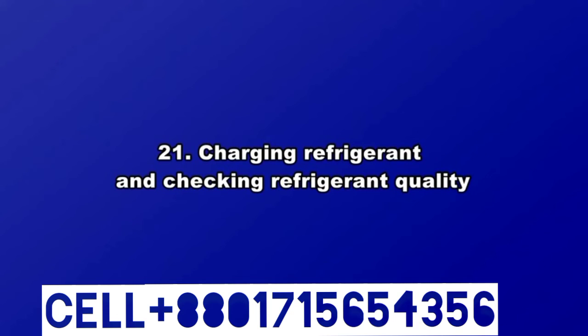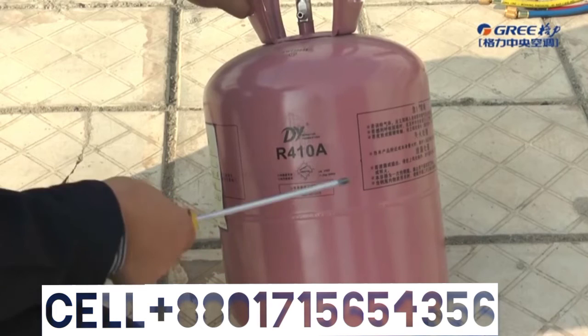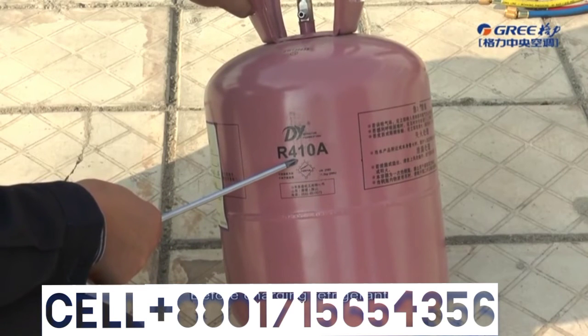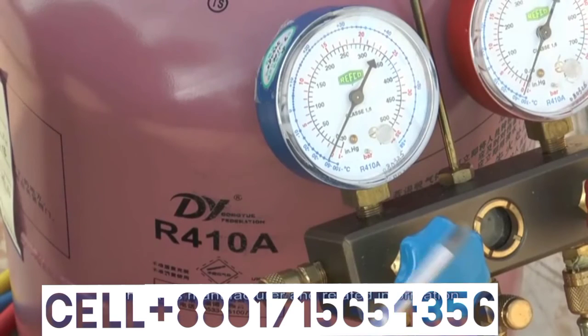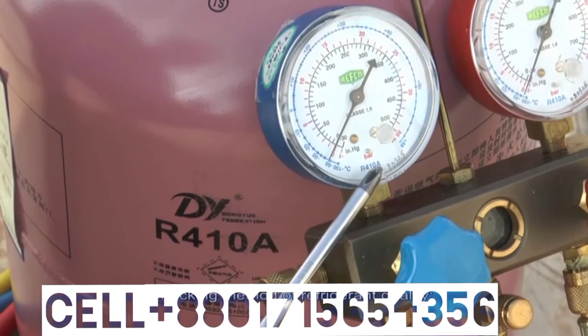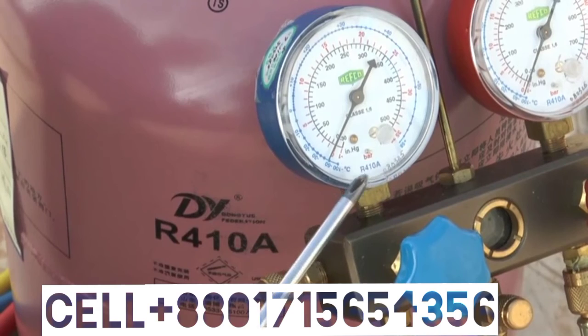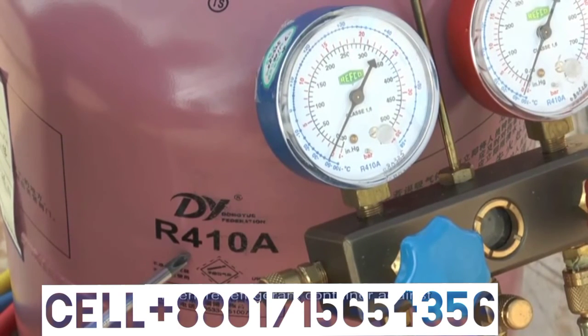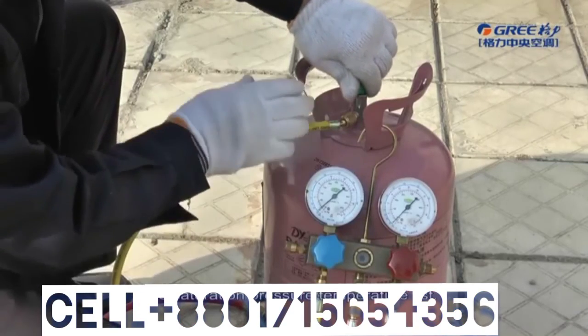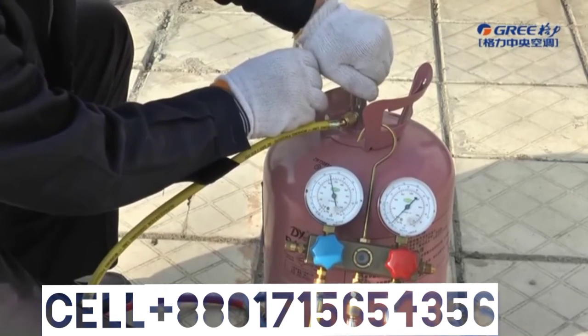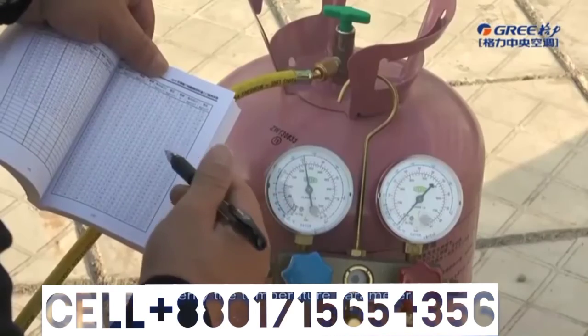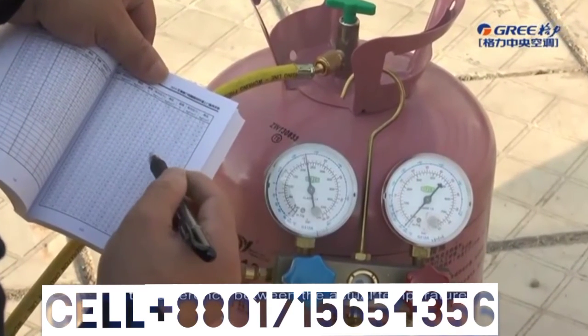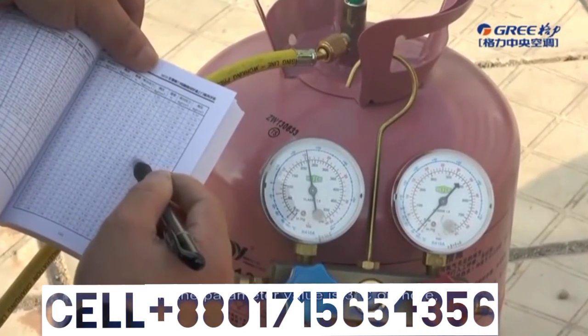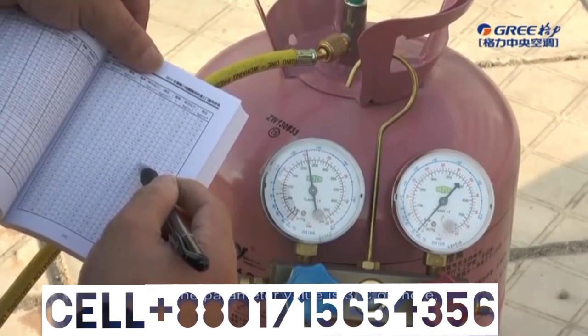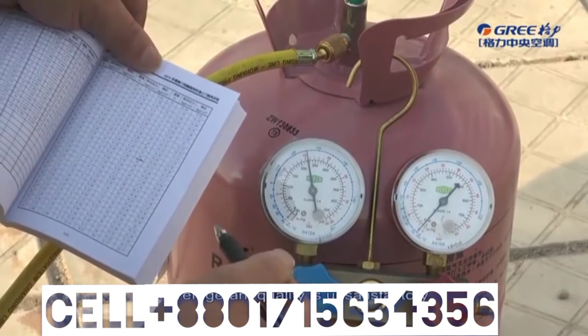21. Charging refrigerant and checking refrigerant quality. Before charging refrigerant, check its manufacturer and related information. Checking method of refrigerant quality. Measure and check the pressure of entire refrigerant container against the saturation pressure temperature list. Verify the temperature parameter. If the difference between the actual temperature and the parameter value is 3 Celsius degree or more, the refrigerant quality is unsatisfactory.